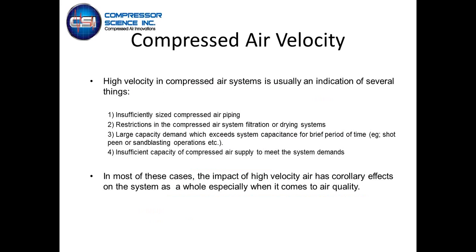High velocity in air systems usually is an indication of basically 4 things that we look at. First, insufficiently sized compressed air piping, which is the largest thing we see. Second, restrictions in the compressed air filtration or drying systems. I was in a plant last week where they hadn't changed the coalescing filters. They were completely pinned in the red, and the compressor had to run at an extra 20 psi just to overcome the line loss. When I opened the bypass on the filtration, the pressure in the compressor literally dropped 20 pounds. So it is a real thing, having restrictions in the filters and dryers.